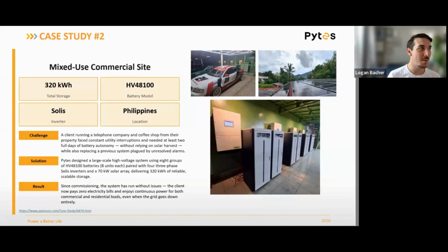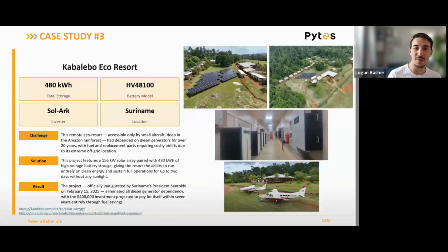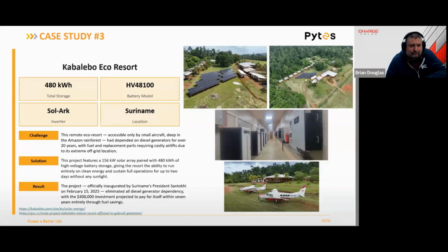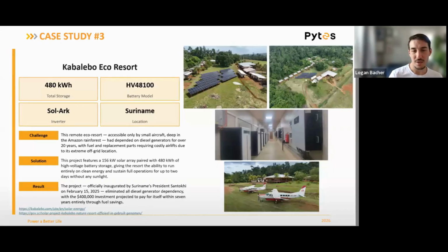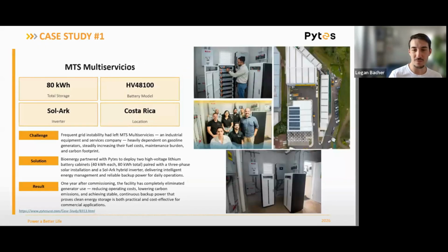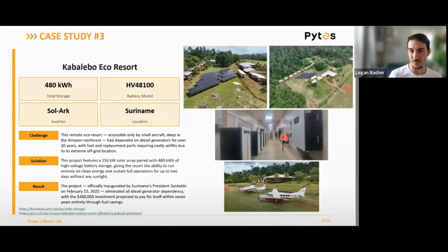The way I would answer it is, that's more of a limit on the inverter side of things, right? So Sol-Ark and Solis, I'm touching on those because that's what we're deploying actively right now. Let's look at this one too, because this one had, I think, 4 or 5 Sol-Arks. Each inverter has its own battery bank. So the inverter manufacturers don't want you, and they actually say you can't, connect two inverters in parallel on one battery. You can do the opposite though. Like I showed earlier, you can connect multiple battery stacks in parallel to feed one inverter, but it doesn't really work the other way, if that makes sense.